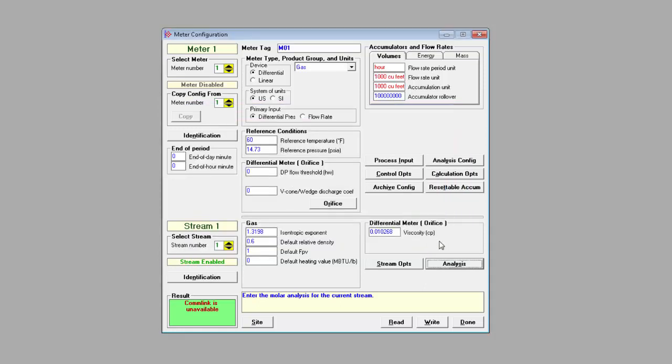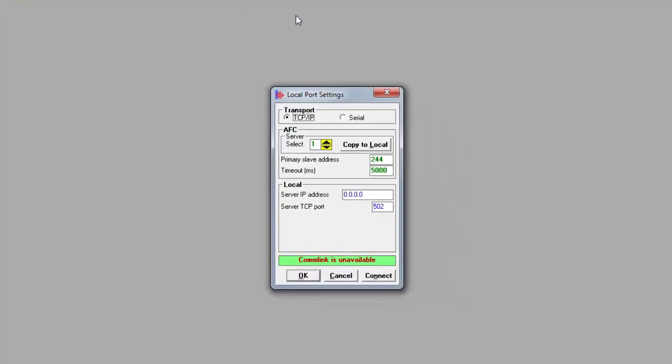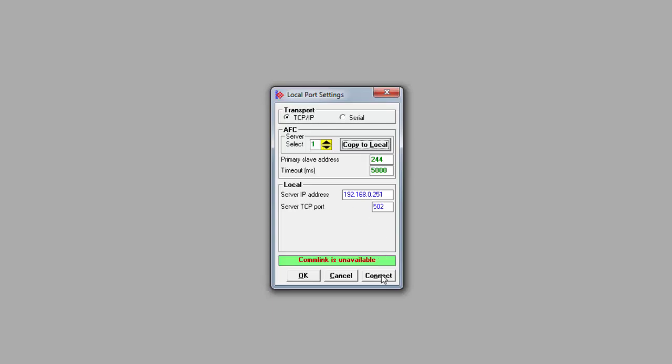Now that our meter runs are all configured, we're ready to connect to the MVI56E AFC module and download our configuration. You can connect using either the ethernet or serial ports. I'll connect over ethernet. Just plug into the ethernet port on the module and connect the cable to your PC or a switch on your network. Under the communications tab, select local port settings. And I'll use the TCP settings. And for the first download, the module still has all its default settings. Click the copy to local button and the IP address field should populate with whatever IP address we configured for that server. In order to connect, your PC will have to be on that subnet with the AFC. Click connect and if all goes well, you should see that the COM link is open.